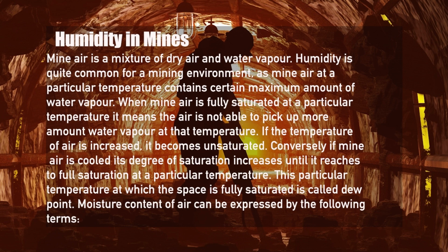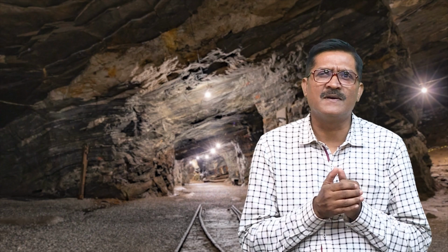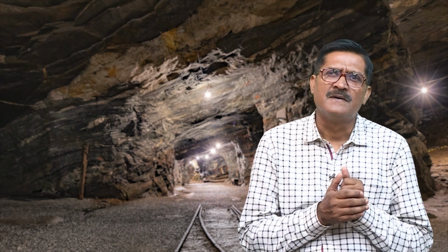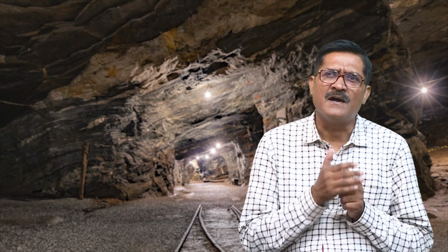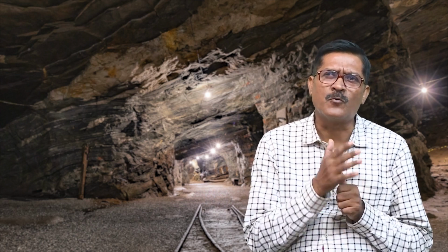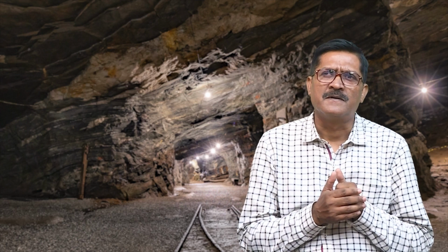If the temperature of air is increased, it naturally becomes unsaturated. Conversely, if mine air is cooled, its degree of saturation increases until it reaches a full saturation at a particular temperature. This particular temperature at which the space is fully saturated is called dew point temperature.